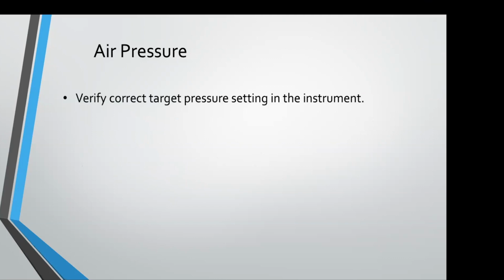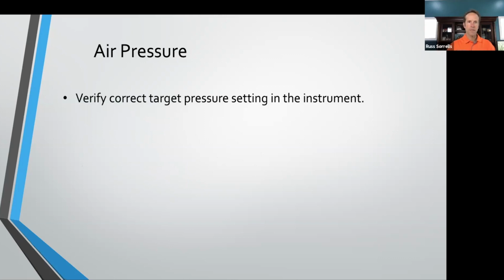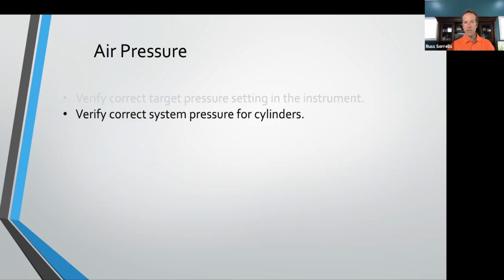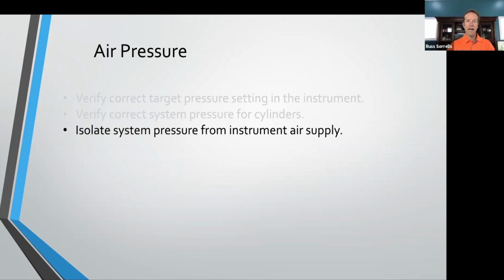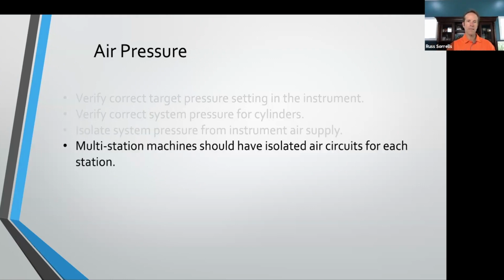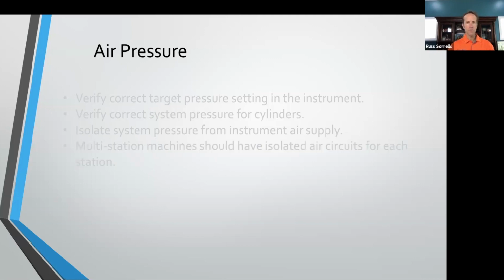Still talking about air pressure, because next to seals, the air pressure is the most common problem. So we want to verify that we have the correct target pressure setting in the instrument. We need to verify that we've got the correct system pressure for your air cylinders that are sealing on the part. We need to isolate the system pressure from the instrument air supply. That is a common thing that I direct customers to do, to isolate that system pressure so that the drawdown on that pressurization does not cause a problem with our leak test. On multi-station machines, we want to isolate circuits when possible from each station, so that we minimize the impact of one station on the other. So those are some common best practices for air pressure settings.